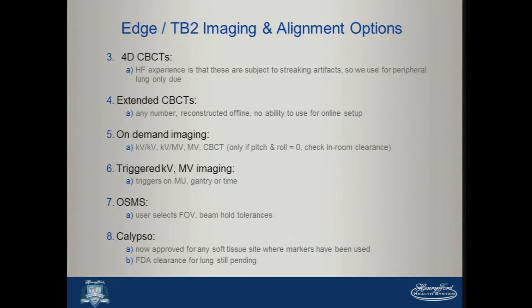The OSMS, again, optical surface monitoring system from 3 cameras, which separately are monitoring the surface of the patient and determining, quantifying the patient position in 6D, and you can select the field of view that you want the system to use, or the part of the patient surface that you want it to use for determining position. And then Calypso, which is now approved for any soft tissue site where markers have been used, although use for the lung is still pending, I believe.